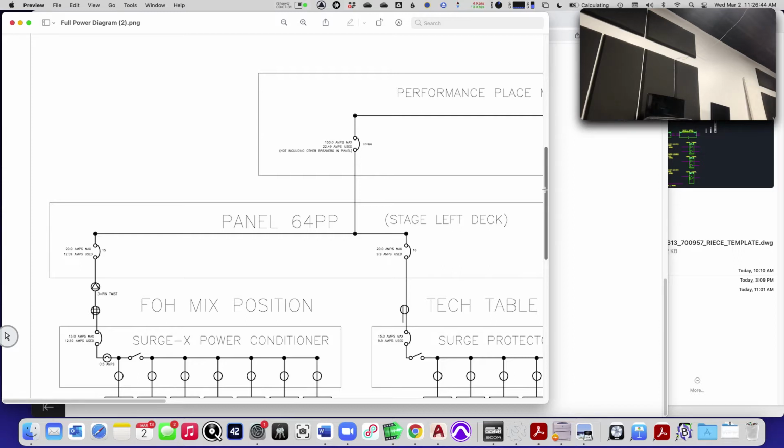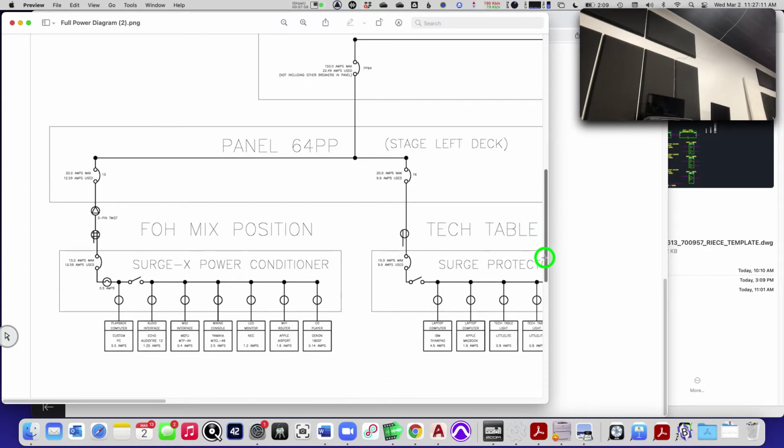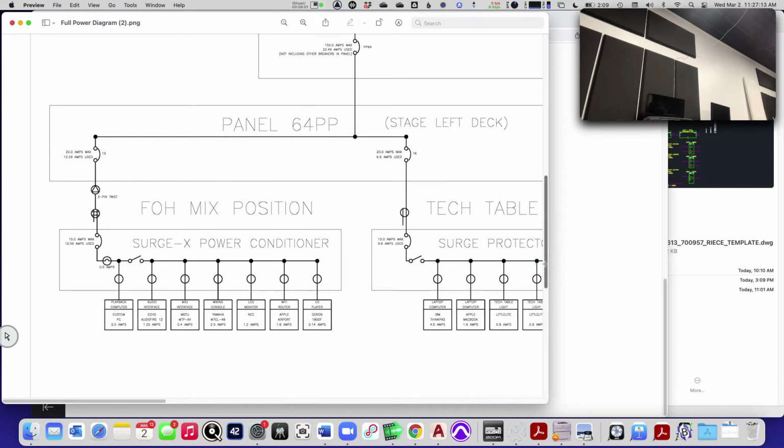Or in most cases, because we're the only ones that do power diagrams, none of the other departments do, we'll always know, and so we will say, well, I don't know. It's a 150 amp breaker. I'm drawing 23 amps off it, so it can't be me that's breaking it, right? And then everyone else has to figure out where the other 125 amps is coming from. Okay. So you just have to plot the stuff you're doing so that you know that you're not the one breaking something.